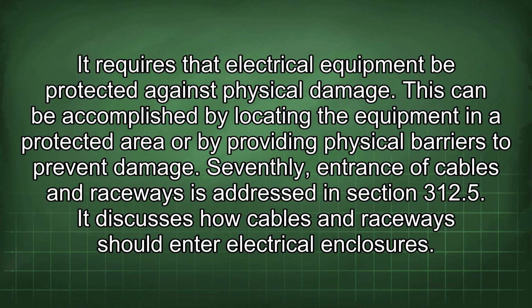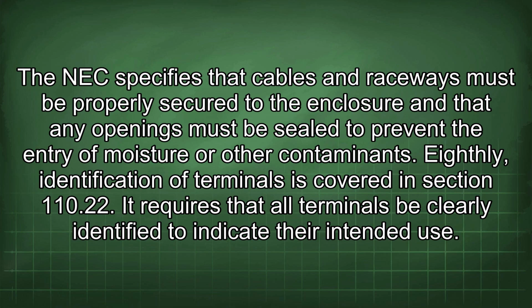Seventhly, entrance of cables and raceways is addressed in Section 312.5. It discusses how cables and raceways should enter electrical enclosures. The NEC specifies that cables and raceways must be properly secured to the enclosure and that any openings must be sealed to prevent the entry of moisture or other contaminants.